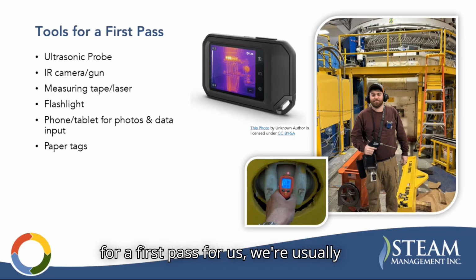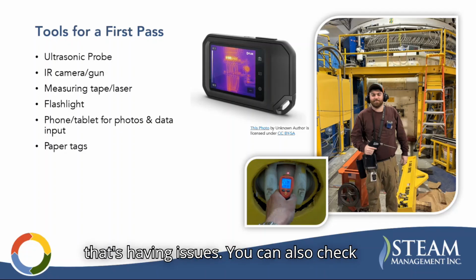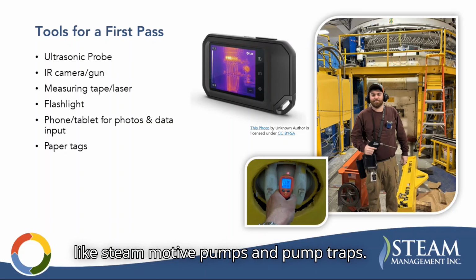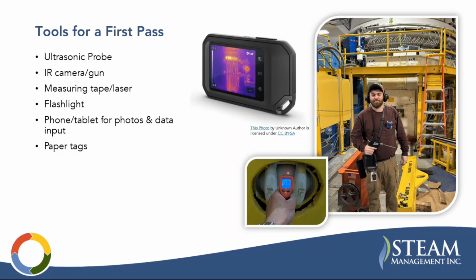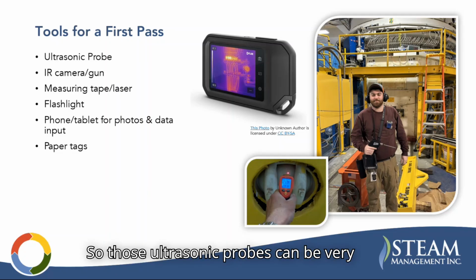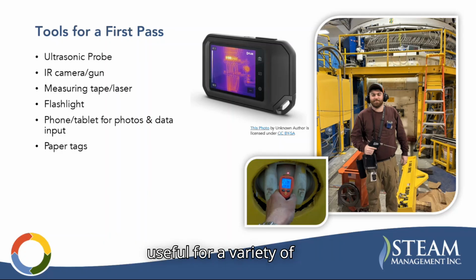Tools for a first pass, we're usually going to have an ultrasonic probe, even if we're not doing a full-on trap test. It's helpful to be able to spot check traps if you see a piece of equipment that's having issues. You can also check steam motive pumps and pump traps. So those ultrasonic probes can be very useful for a variety of things.